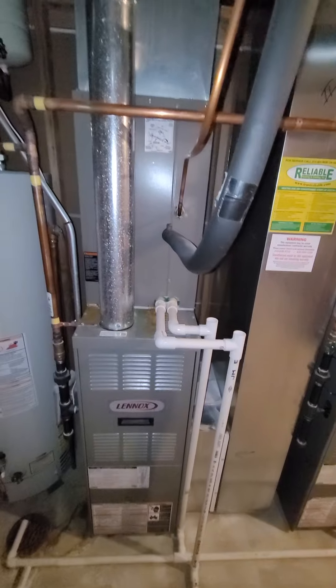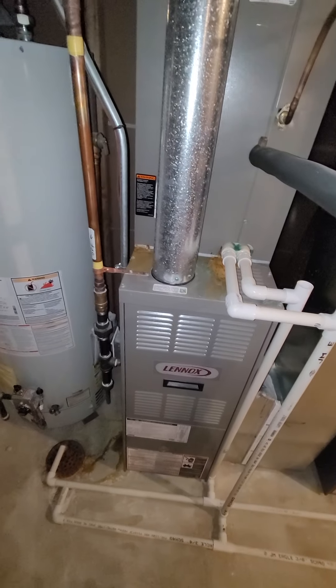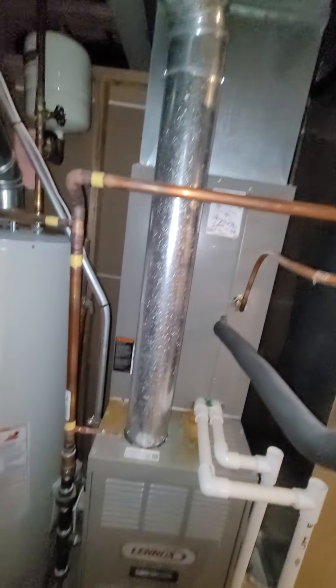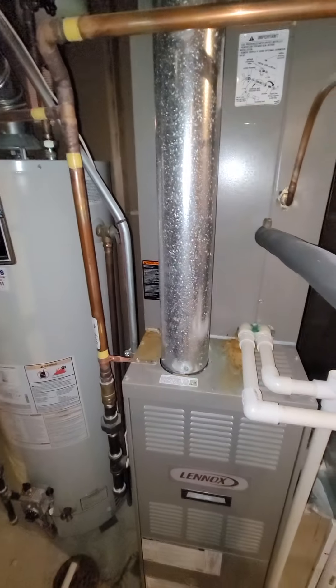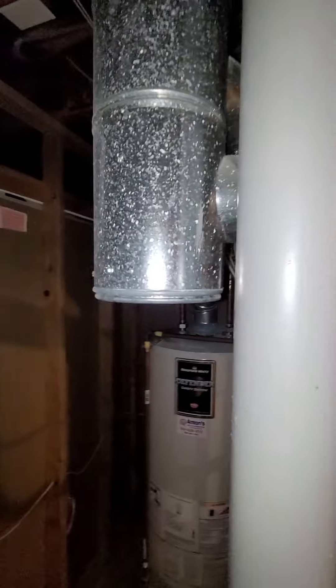You've got about 43 inches between here and the top — that's the width. Got a copper gas line coming right in front of the unit, and so is the flue. You have a four-inch, four-inch, four-inch, and water heater going into a six-inch clean out.